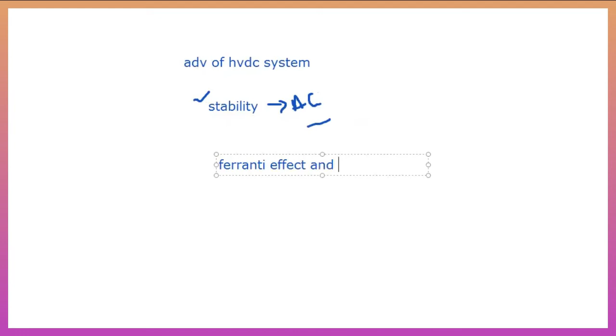That's why this is one of the major advantages of the HVDC system. There is no Ferranti effect and no skin effect, which are issues caused by the AC system — a reactance problem and a charging or capacitance problem. Because of this, the receiving end voltage will be greater than the sending end voltage, and due to the skin effect, current concentration will be more towards the surface of the conductor.